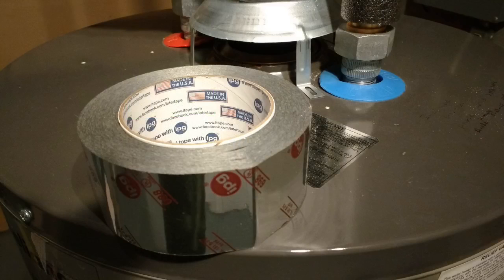Sealing those joints should never be done with duct tape. Duct tape is probably the worst thing you can use on ductwork because the adhesive dries out over time, it turns to powder, and the tape falls off and you still have a leak. By all means, use a tape that is designed to seal steel ductwork. And when it's sealed, it should look something like this. Every joint, every place where steel meets steel should be sealed. All of it has to be sealed, no matter how small the joint appears to be, because they all leak and they can add up to very big leaks.